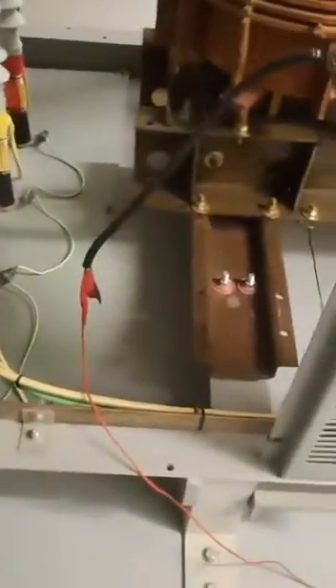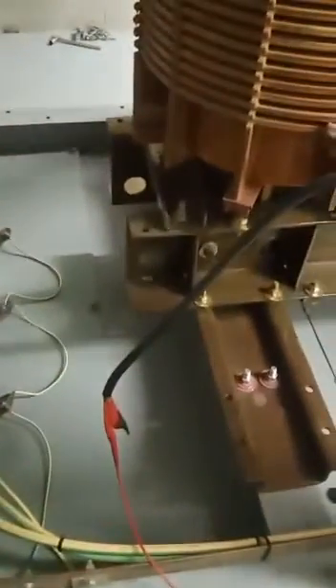Now we are going to start the test. Actually, the test will be carried out HV to earth, LV to earth, and HV to LV winding. Now we are going to test the HV to LV winding. The test lead is connected with the HV side winding. One lead is connected with the HV side, and the other lead is connected with the LV side.